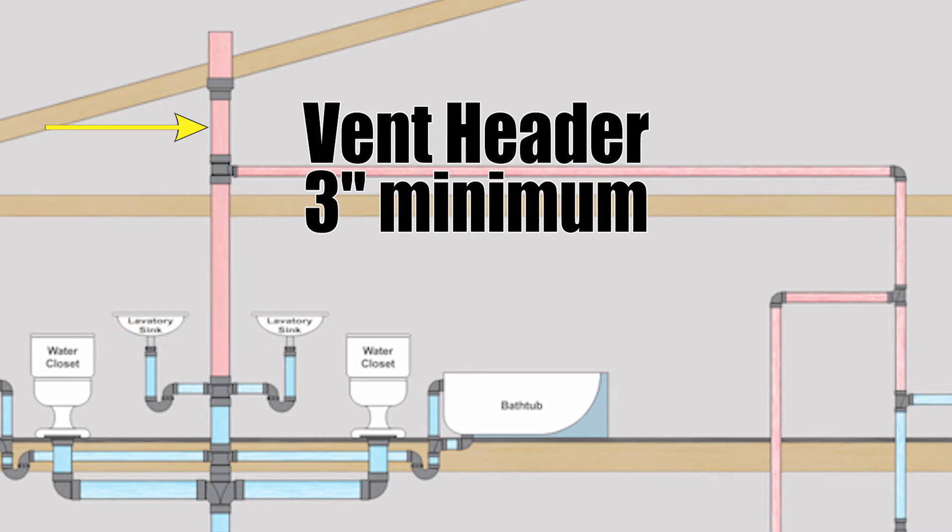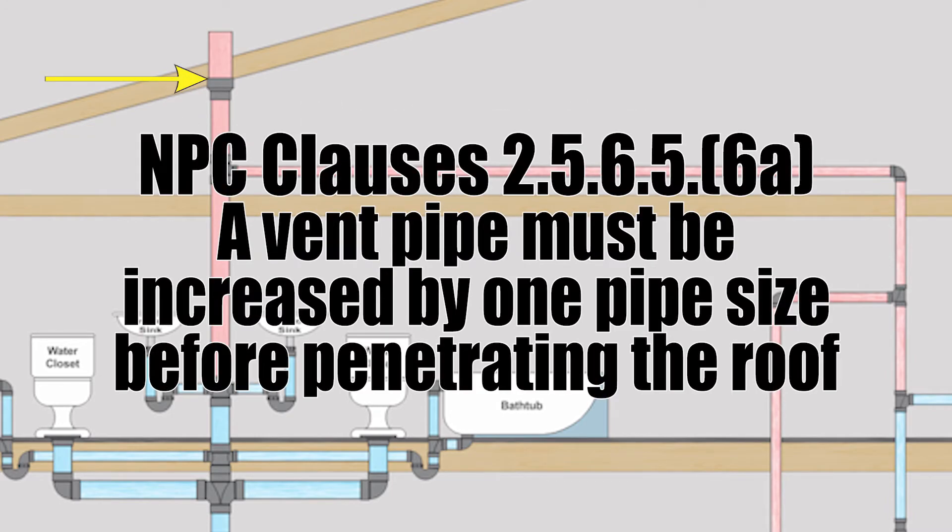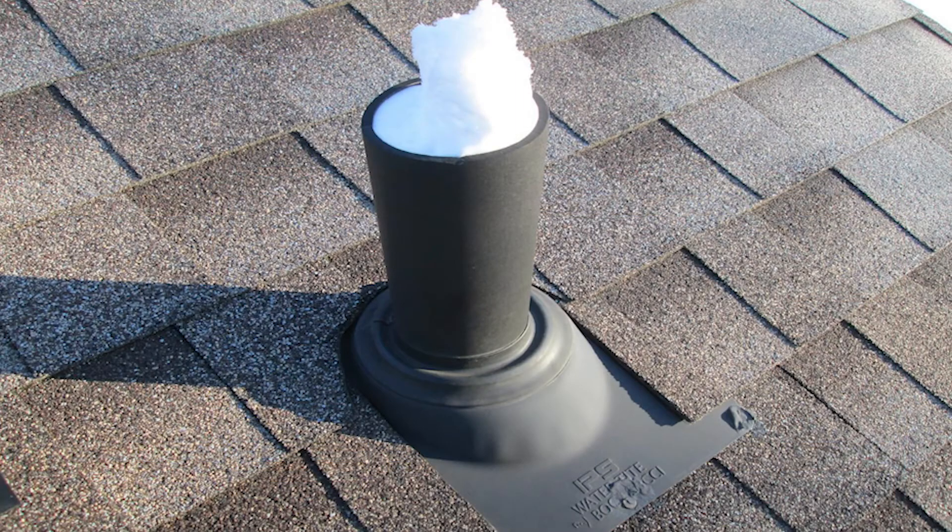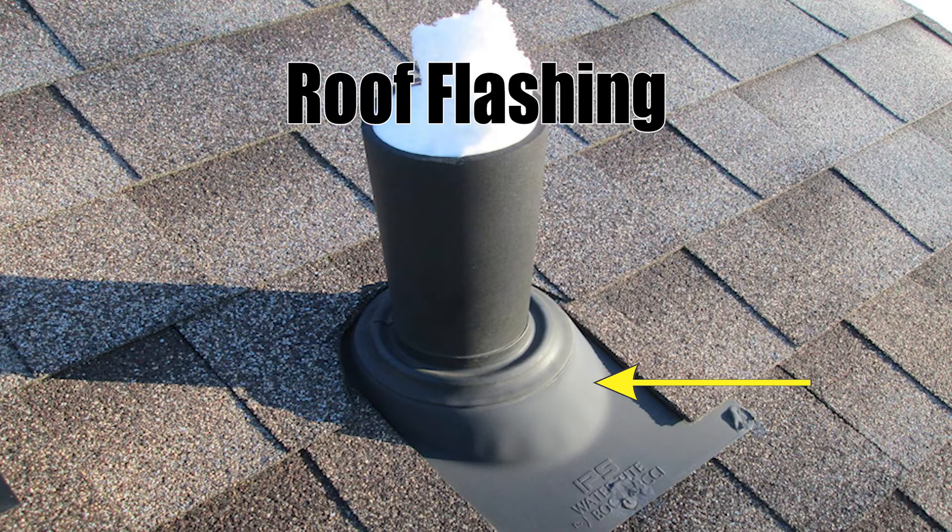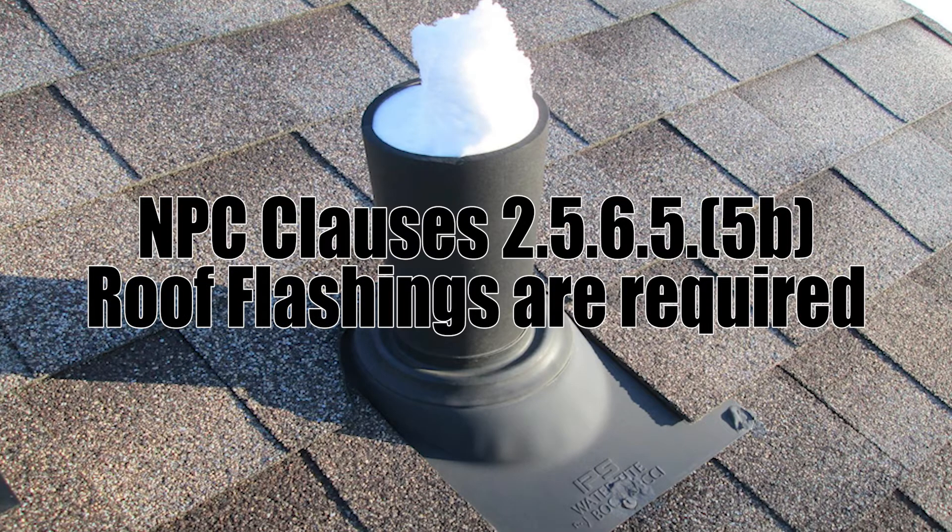So yes this vent header will be three inches in size and it will increase one pipe size before passing through the roof. Now this is to prevent frost closure on cold winter days in areas like where I live. This rubber device that goes around the pipe and goes underneath the shingles is called a roof flashing. This prevents rainwater from coming down around the pipe and making its way into the building. It makes a watertight seal.